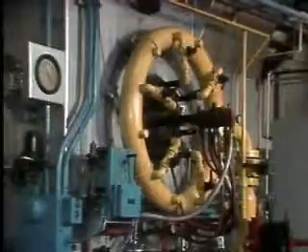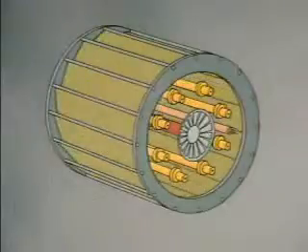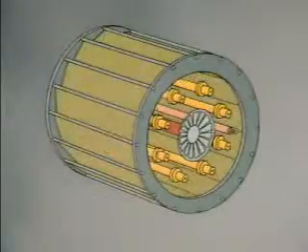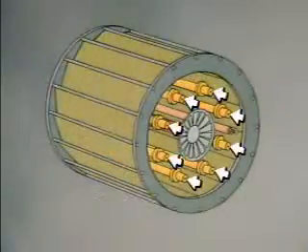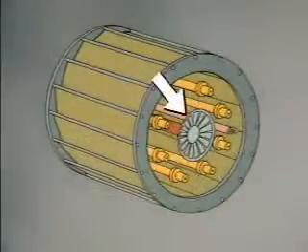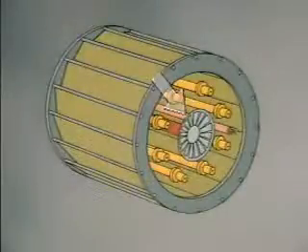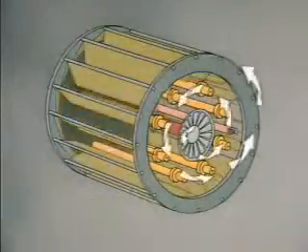The main function of all burners is the same: to inject a mixture of fuel and air into the boiler's combustion area. Burners are used with fuels that mix easily with air, such as natural gas, oil, or pulverized coal. A typical gas burner uses dampers or registers to regulate the amount of air entering the burner. Pipes called spuds inject natural gas into the boiler. An impeller — a stationary plate with openings or vanes — causes the air to swirl around and thoroughly mix with the gas.